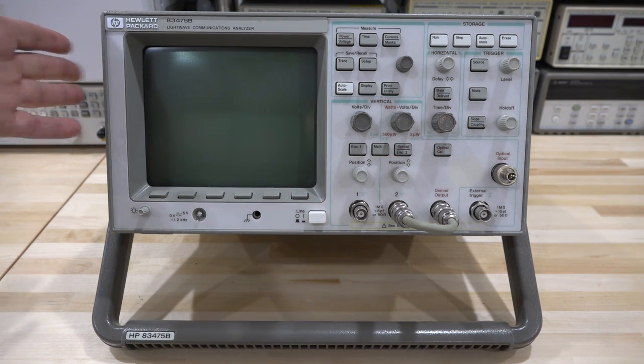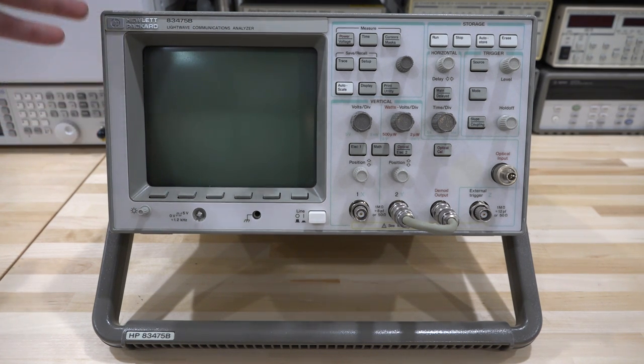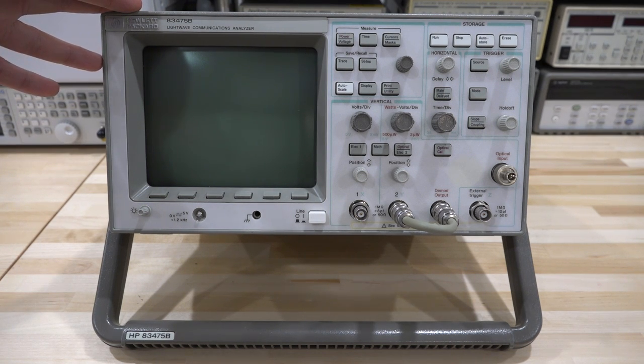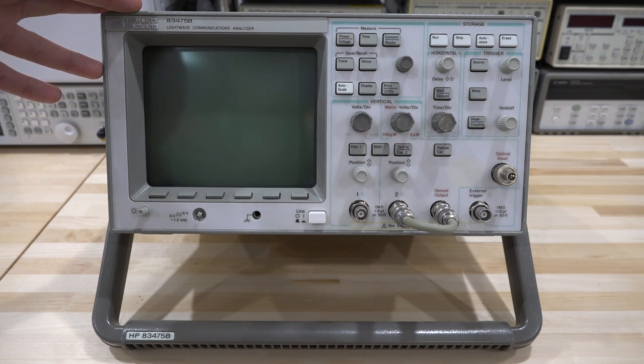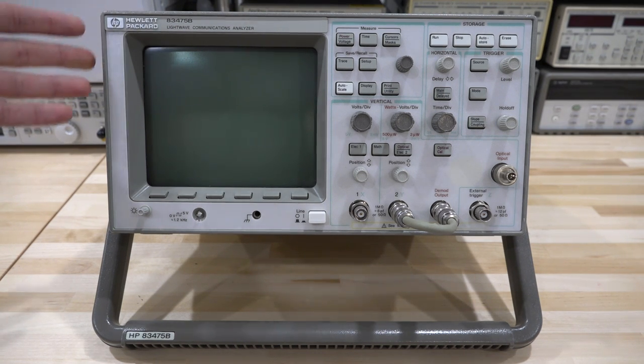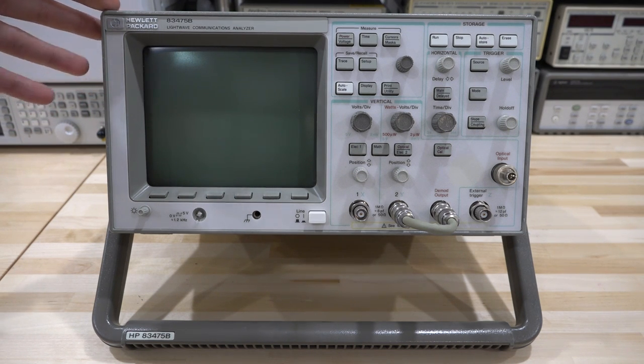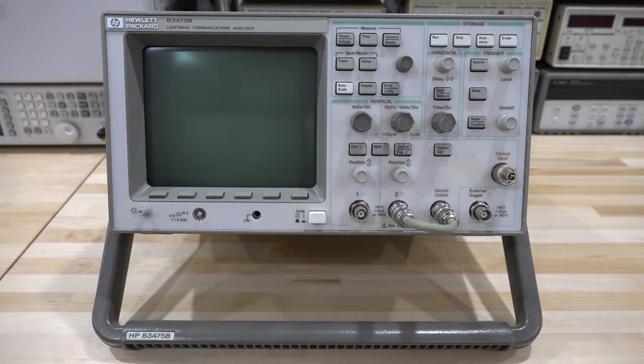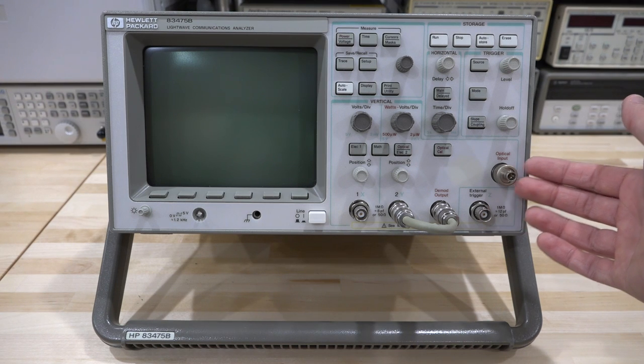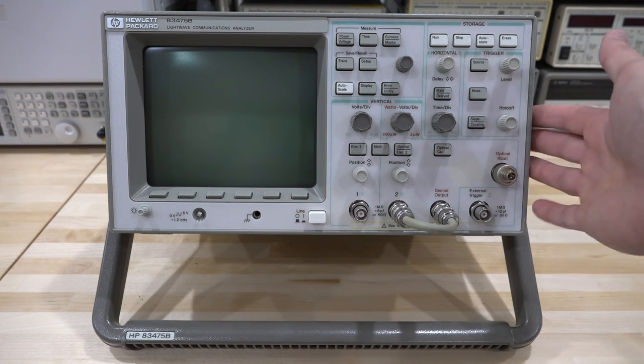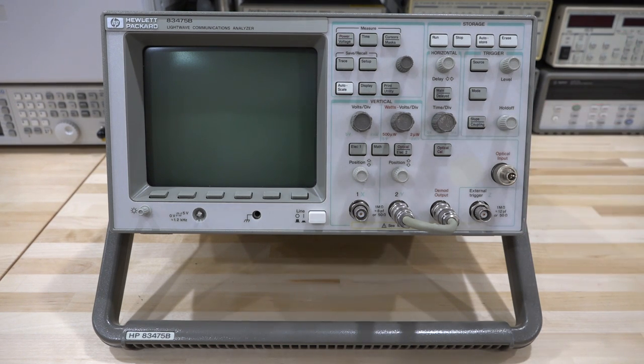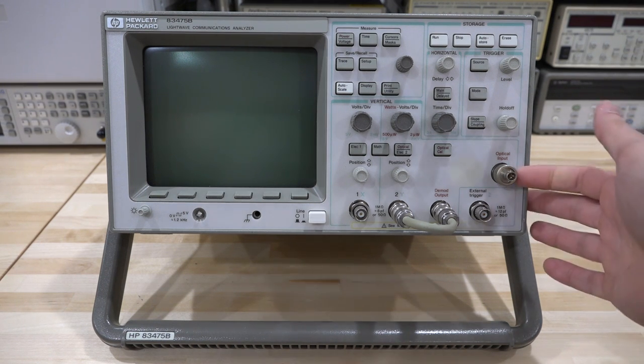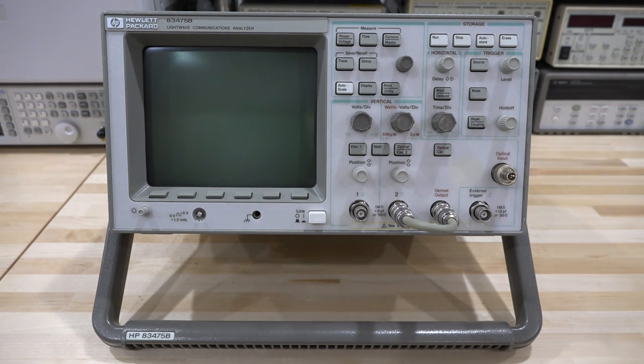Now this looks like a pretty old unit, and that's because these guys evolved to eventually become the DCA and the DCA-X. If you're not in the optical communication industry, you may have never seen one of these, because this guy actually has an optical input directly on the oscilloscope itself, and this is the reason why I thought it's worthwhile taking a look at for repairing, because of the optical input.